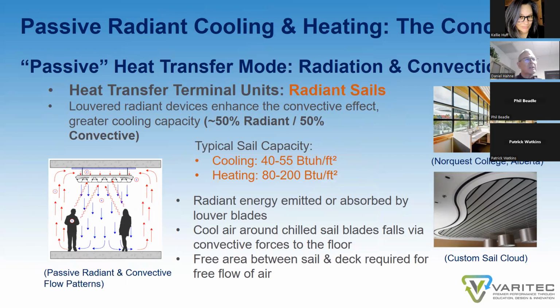The other type of product that's available for passive radiant technology are radiant sails. They are louvered devices that enhance the convective effect. They allow air to pass through them. And the actual radiant component are louvered fins that are assembled together in rectangular or custom arrays that not only emit radiant energy from a warm surface or absorb space-side room energy by creating a cooler surface, they will also allow air to more freely pass through the device through the forces of convection. So consequently, the convective to radiant effect on a sail is about 50-50.